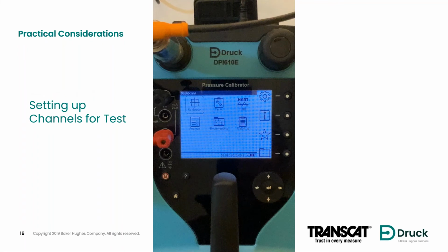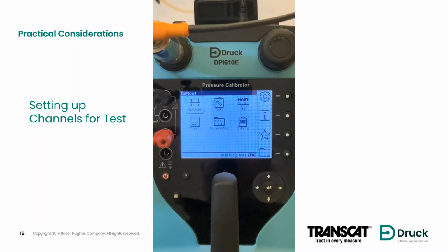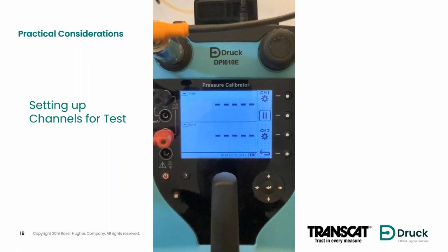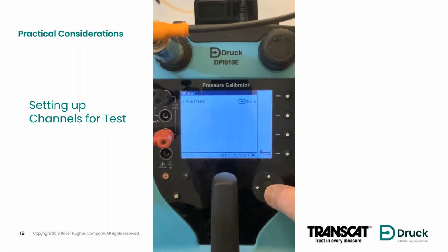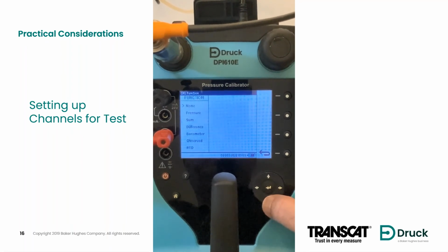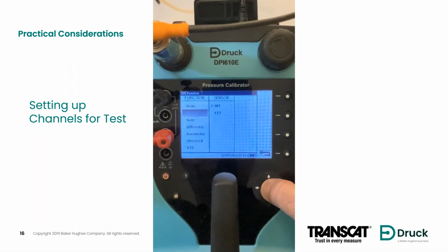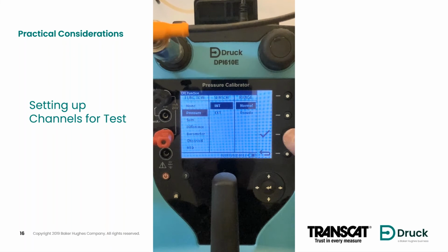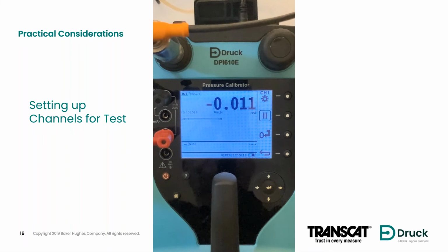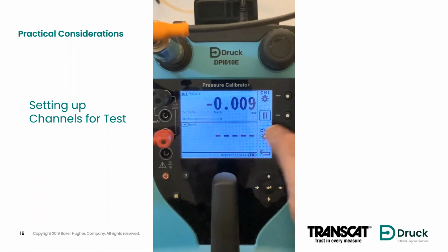So now I just wanted to go through this video setting up the test channels, the channels to actually perform the test. So showing the screen going into the calibrator mode. Right now both channels are set to no function or none. So this is the pressure channel that I'm just setting to pressure to use the internal reference sensor and to use it in the gauge mode or normal mode. We do have an internal barometer that we can add to gauge measurements to do absolute as well.